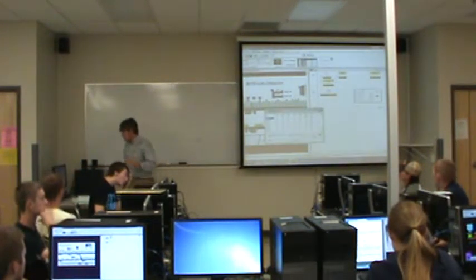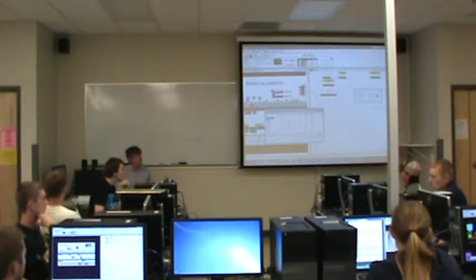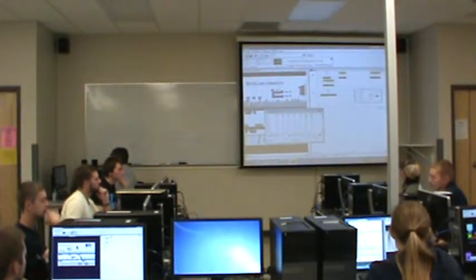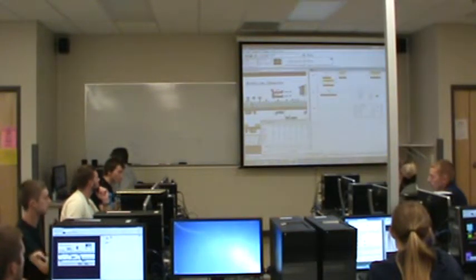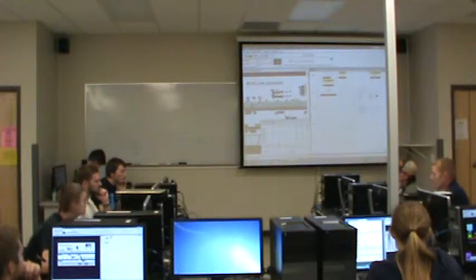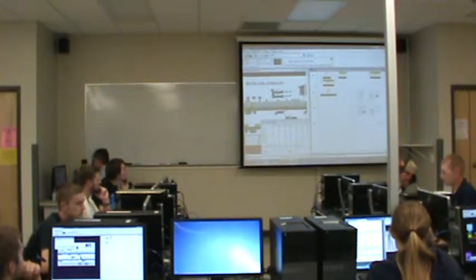Okay? Now, that's not very good practice most of the time. It'd be better if I want to increment the counter for another reason, to have an OR around that. Okay? But anyway, in this case, I'd like to decrement the counter. So it turns out that there is an instruction for counting down. Now, what I'm going to do is reference the exact same counter. Because like I said, the counter is really something that is in memory.